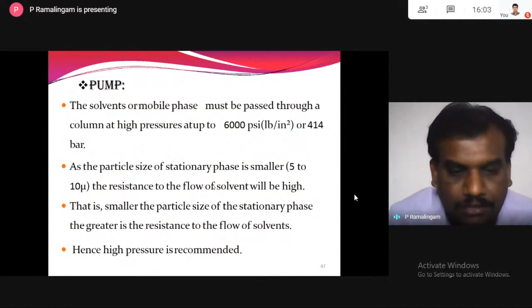So the requirement of the HPLC pump is, as I told you, that the pump should be able to generate 5,000 psi, and should deliver the solvent pulse free. Pulse free means the velocity or flow of the solvent should be stable. It should not be up and down. And flow rates should range from 0.1 to 10 ml. Usually in an HPLC system, we require up to 2 ml. That's enough, not more than 10 ml. 10 ml is more commonly used for preparative HPLC.